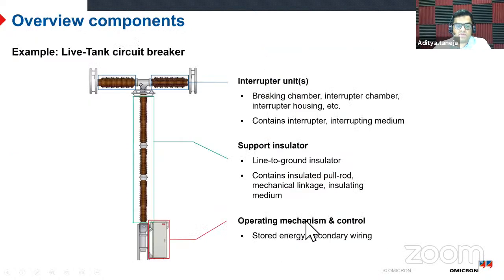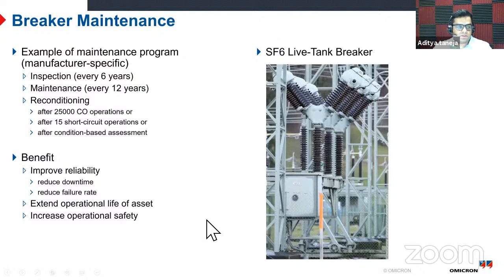So there is something which has operating mechanism and control, where the command from the relay will come, and it has the spring or whatever is the mechanism to store the energy. Now with this, I can take this very simple functional model to other breakers also, may it be GIS, may it be vacuum. I can go back and relate the same things to those breakers. I'll not go into taking this to other breakers, but this is a model which I will use for my further discussion.